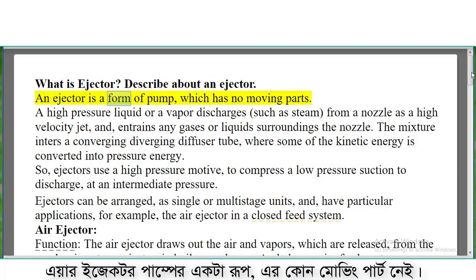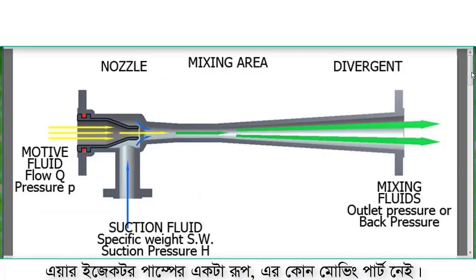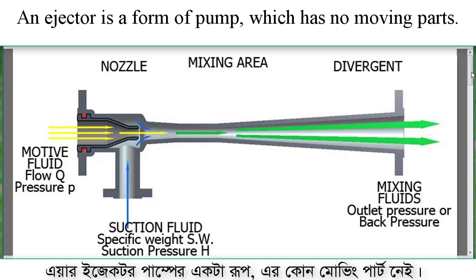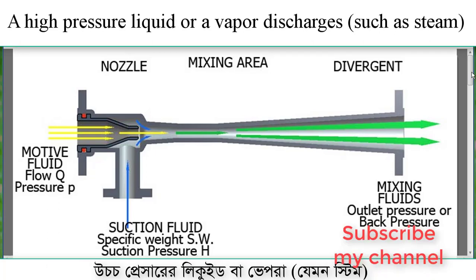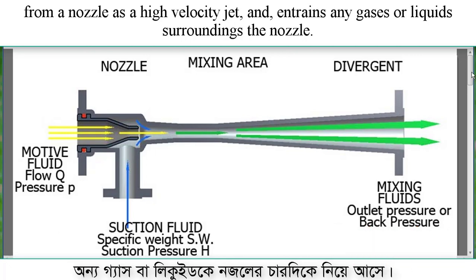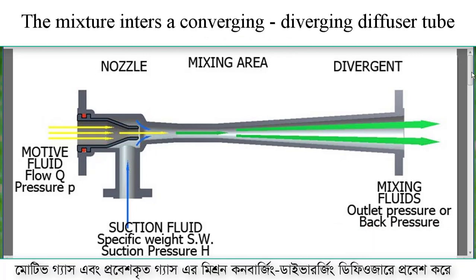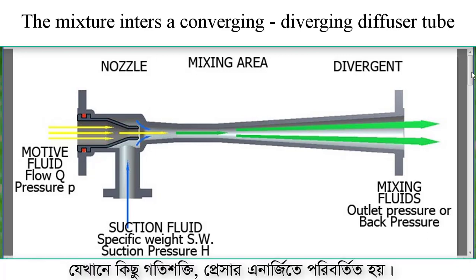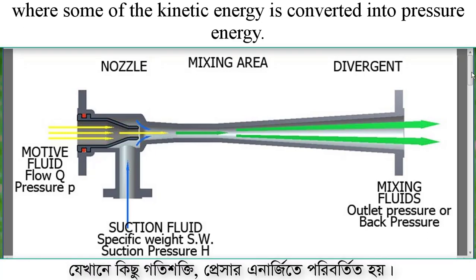An ejector is a form of pump which has no moving parts. A high-pressure liquid or vapor, such as steam, discharges from a nozzle as a high-velocity jet and entrains any gases or liquid surrounding the nozzle. The mixture enters a converging-diverging diffuser tube, where some of the kinetic energy is converted into pressure energy.